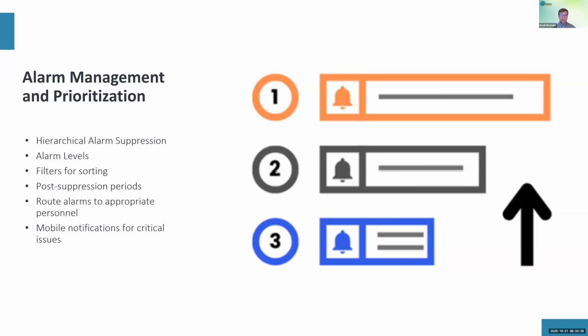We can also assign different alarm levels that essentially do the same thing. ASHRAE 36 recommends 4 different alarm levels. You have life safety, critical, urgent, and normal. And those levels indicate to facilities how pressing of an issue it is, the urgency in which they need to generate a response, and the severity of the alarm. We can also tag alarms with things such as date and time, equipment affected, etc. And that allows for when there's a laundry list of alarms, facilities can sort through those to help them prioritize their responses. Alarms can be routed to appropriate personnel, and mobile notifications can be generated for critical issues so they're not missed.